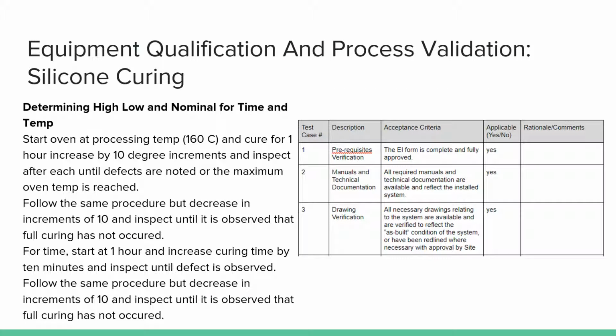In order to validate the silicone curing process and equipment, IQ and OQ acceptance matrices were made. To the right is shown a snapshot of the IQ acceptance matrices, and then testing was done to determine high, low, and nominal values for time and temperature for silicone curing. This was done by starting the oven at the processing temperature of 160 degrees Celsius and curing for 1 hour, increasing by 10-degree increments and inspecting after each curing until defects are noted or until the maximum oven temp was reached. The same procedure was followed, but in decreasing increments of 10 degrees and inspected until it was observed that full curing has not occurred.